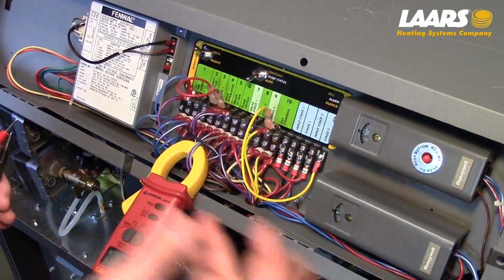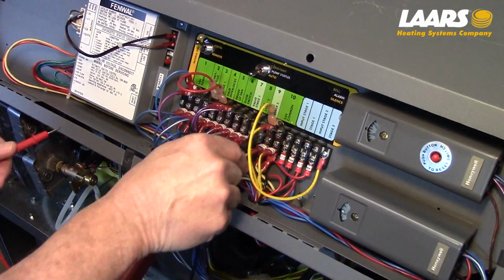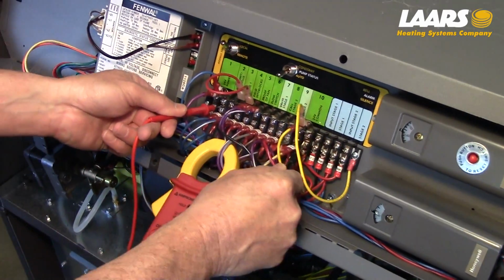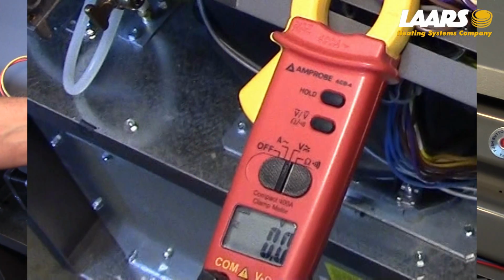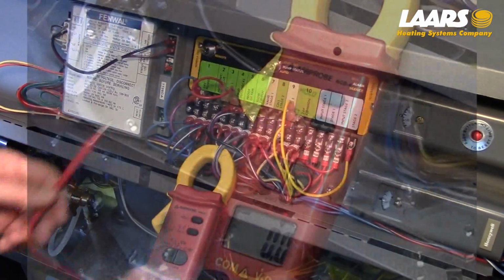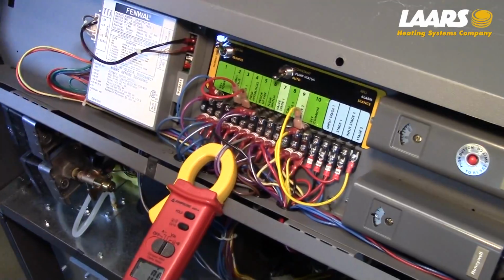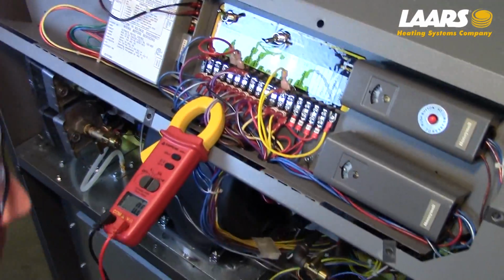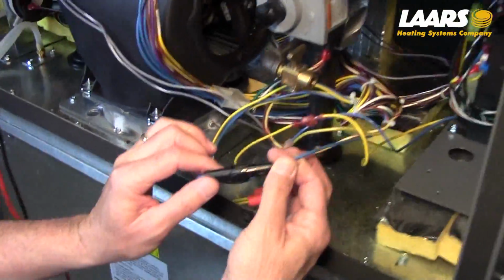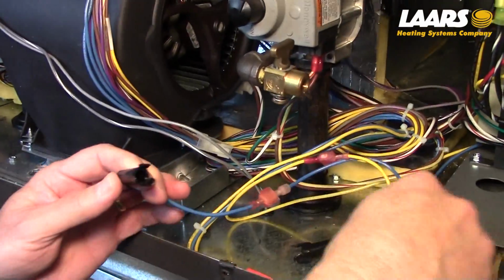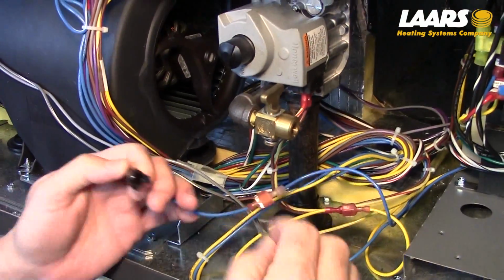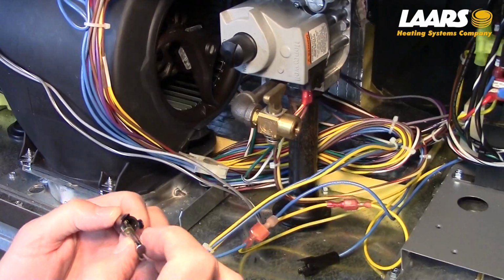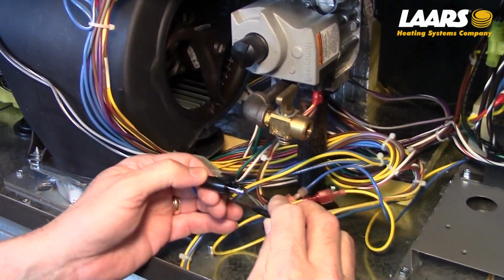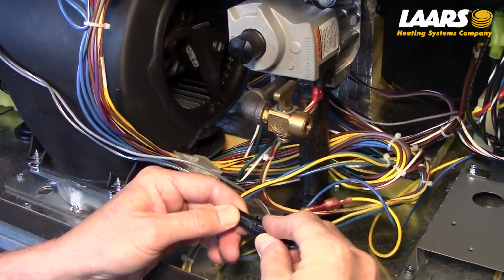And in this case, I do have power coming into the boiler, but as you can see, I do not have 24 volts between terminal 1 and terminal 10. So, what's in line there is our transformer and a bus fuse holder. And for this example, I simply took the fuse out of the boiler. Okay? So double check your fuse if that's the case. I'll put this back in.